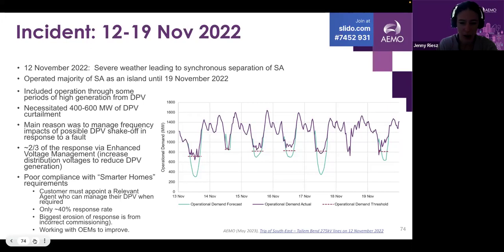And you can see on the right there the operational demand or the net demand levels that we were measuring for South Australia. The teal color is what was forecast, and the purple is the actuals. And you can see that we've trimmed off the troughs by curtailing distributed PV through the middle of each day. The dashed lines there are the targets that AEMO was instructing our network providers to meet. So we were curtailing off about 400 to 600 megawatts of PV throughout some of those really high PV days.